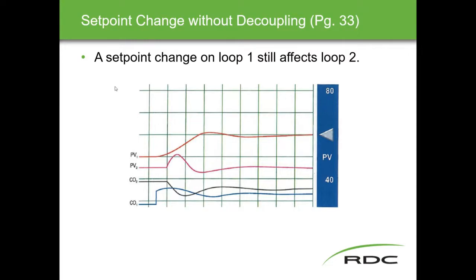The next few slides show what happens with and without decoupling, and when loop gain is greater or less than one. First: a set point change with no decoupling. A step change in the set point on controller one caused a response from both PV2 and PV1. Obviously no decoupling, because the change in one controller had a change in both variables. The least you would expect with decoupling is to have one variable stay steady — that's the whole point of decoupling.